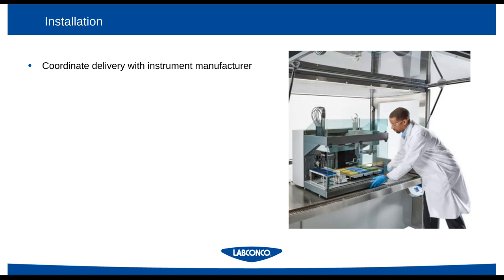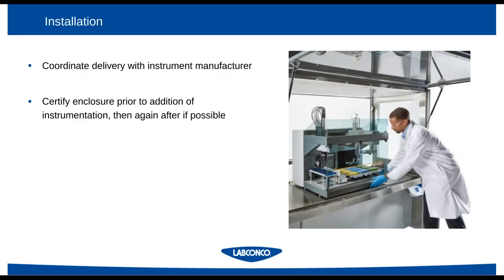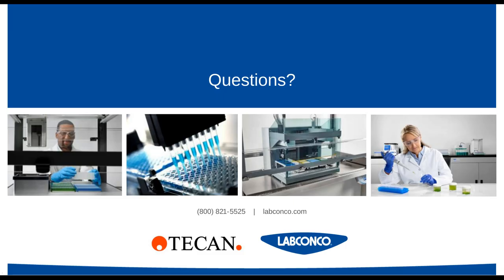Again, on the installation side, that means coordinating both with Labconco on the delivery of the instrument, also coordinating closely with the automation platform. We find the best integrations are where the users of the instrumentation are closely working with the automation enclosure and also the automation equipment providers, specialists, to ensure that all pieces of equipment arrive on time and are successfully integrated together. And again, test the unit before it's loaded with automation, and then again at the delivery and completion of installation of the automation system.